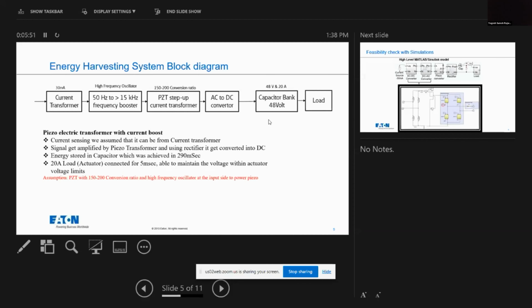This is given to the capacitor bank, where we charge the capacitor bank to 48 volts at 20 amperes. This 48 volts and 20 amperes is needed to power on or actuate the main contact, which I explained in the hybrid circuit breaker block diagram, and ultimately the load.